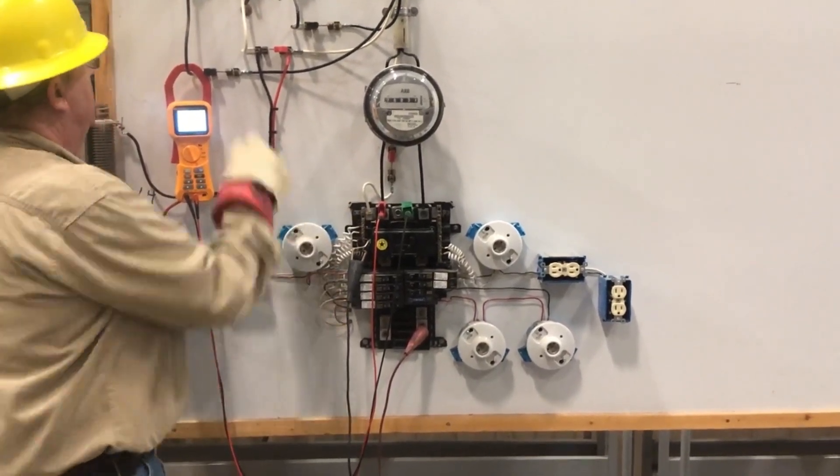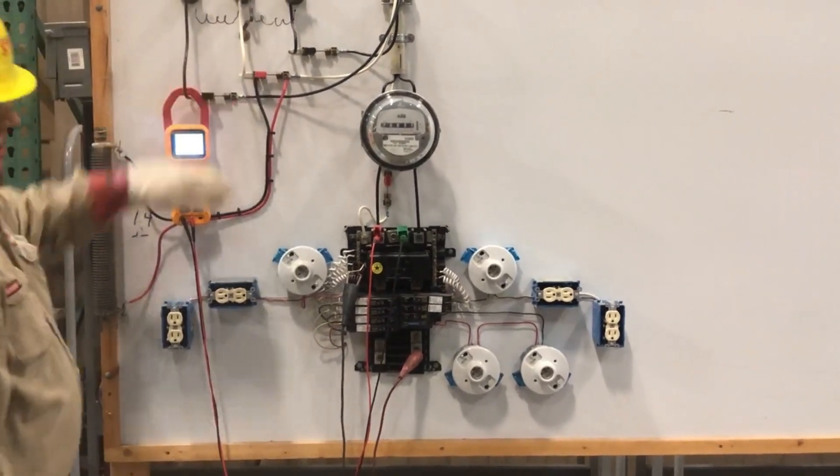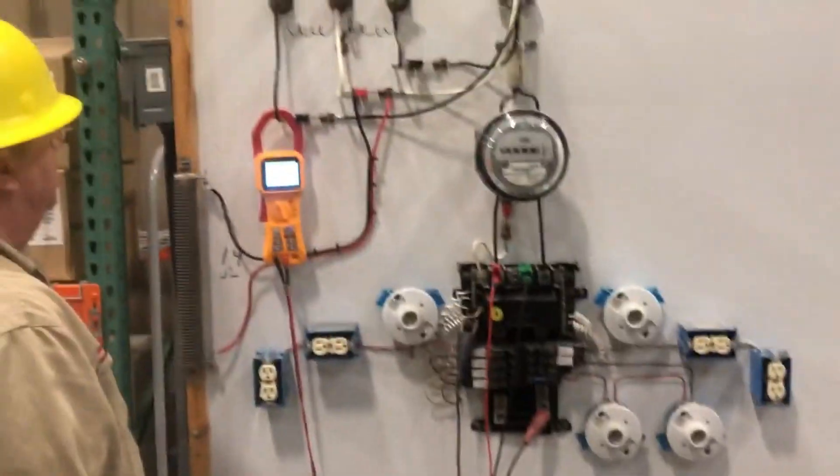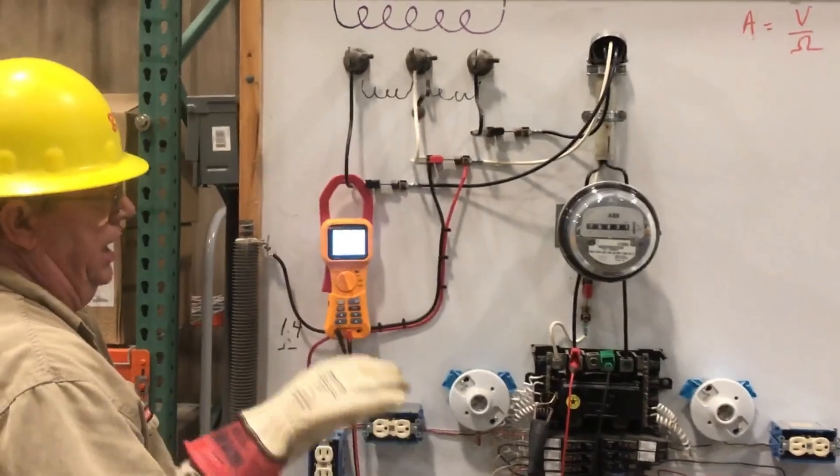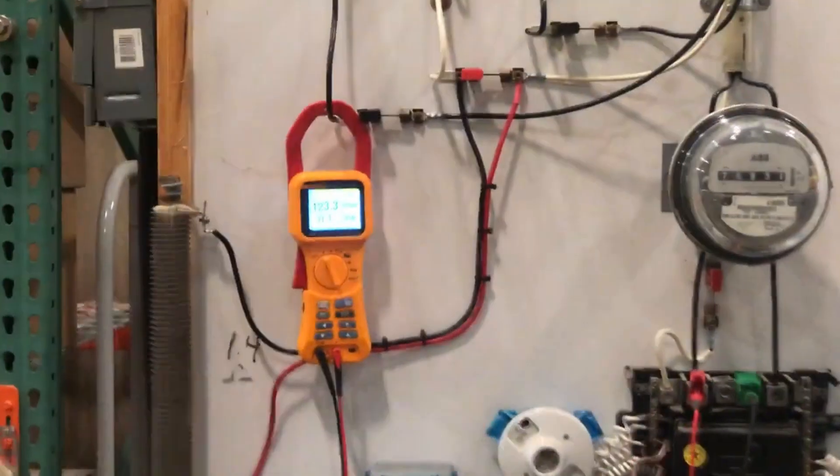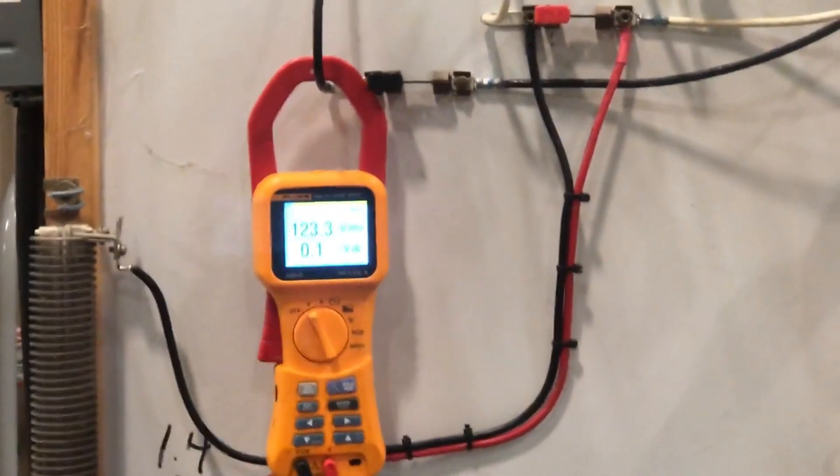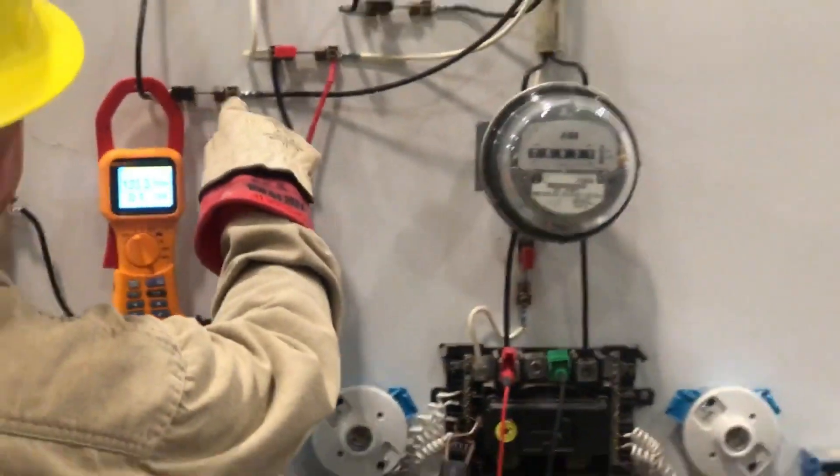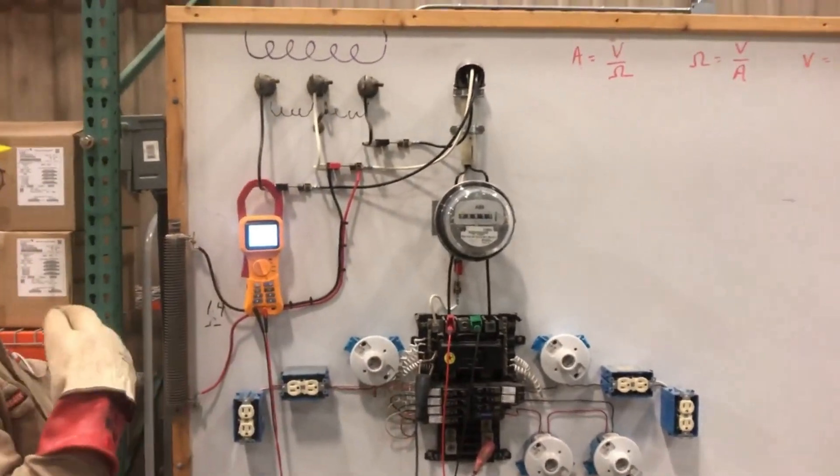Now I'm going to bring on load with the neutral closed. The neutral is in good condition. 121.6, 122.7. And you're watching the loaded leg or the unloaded leg. 123.3. Neutral is in good condition. We added 24 amps and we watched the unloaded leg go to 123.3.